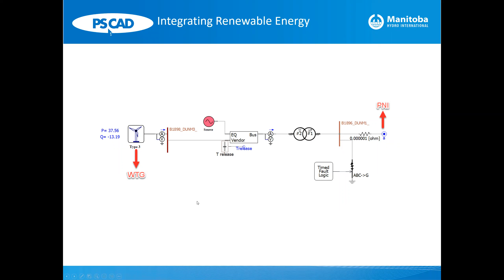When you've designed your network - here this shows part of a utility scale network developed in PSCAD - we can apply faults or short circuits and compare them with field measurements or against the software used to import the data. Generally, we apply faults, look at measurements, and compare against known data.